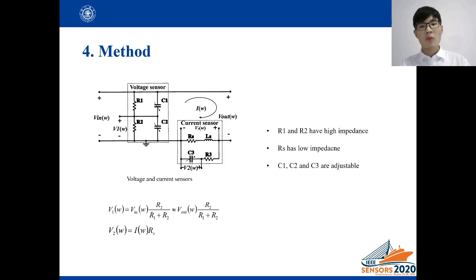The output of voltage sensors and current sensors are calculated as the following equations. C1 and C2 are manually adjustable capacitors to eliminate the effects of the parasitic components of R1 and R2. In the same way, C3 and R3 eliminate the effects of the parasitic inductor of RS.